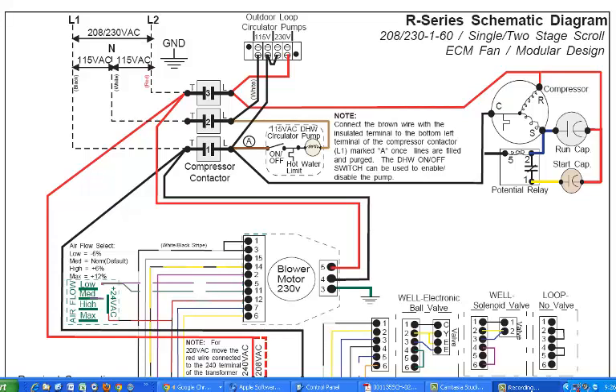What we're going to do is begin up in the upper left-hand corner of our diagram here, and note that what we've got showing up here is three terminal points. We've got L1 and L2 and then N. The meaning of those would be L1 is line 1 coming in, L2 is line 2 coming in, and if we were to take a voltmeter and measure across those two, we should see somewhere in the range of 230-ish volts.